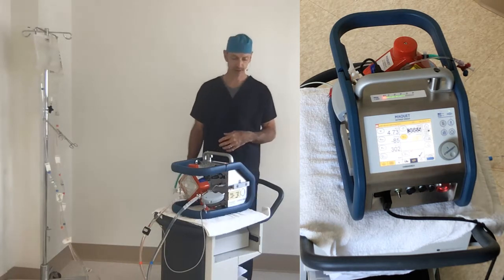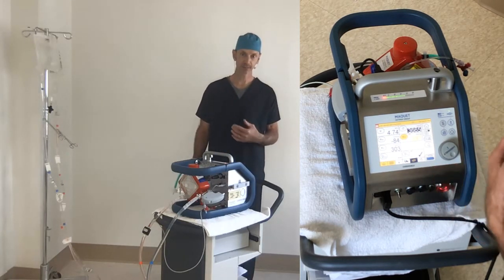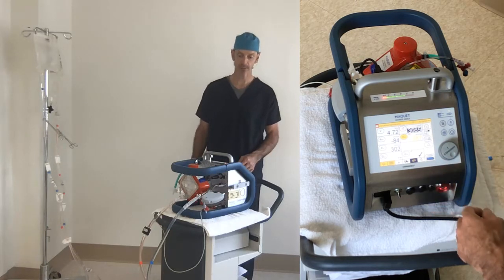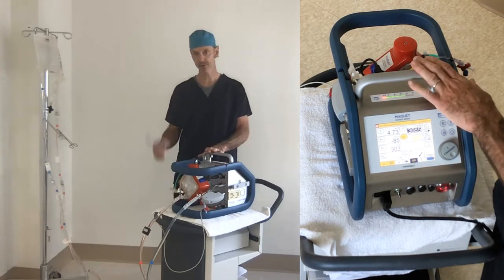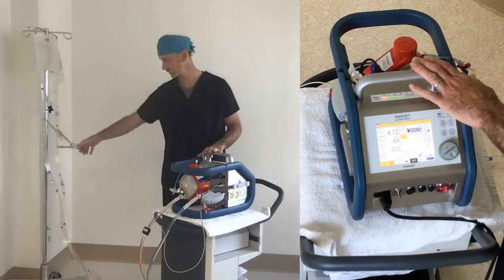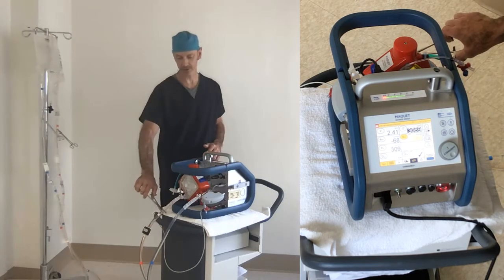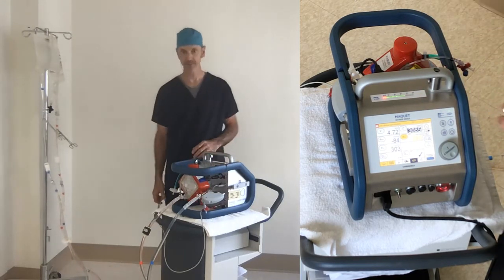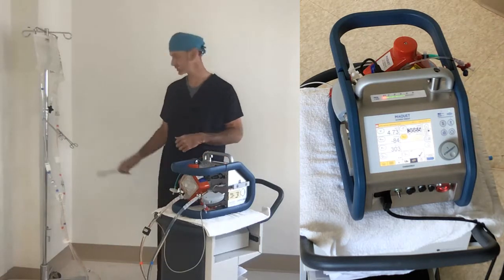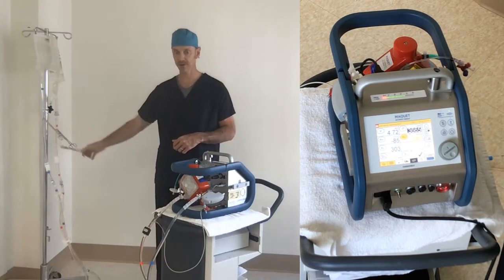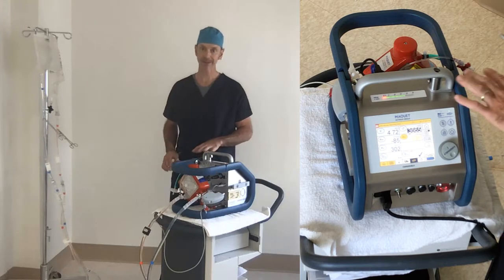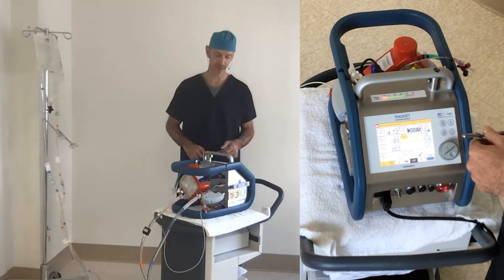Hopefully your people in the room at the time interact with that in the proper way, that any time the pump stops, we need to get a clamp on the line. Clamp the arterial line. You could clamp the line over here, over there, it doesn't matter. Arterial bubbles, we suggest clamp the art line close to the patient. Just a normal pump stop, clamp it anywhere. You just want to prevent retrograde flow.